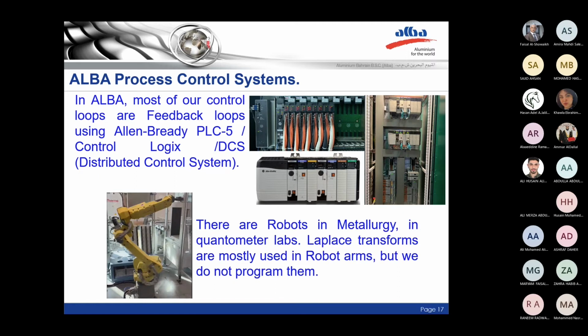There should be an alternative that starts from where the previous control stopped. That's why there are two PLC chassis, or ControlLogix chassis, with the input and output module connections through the flex IO going to the control Ethernet port, Ethernet card, and from the Ethernet card connected to the controller. These are the redundancy.